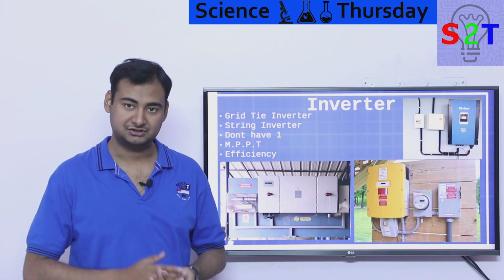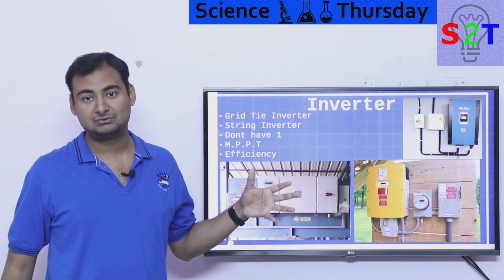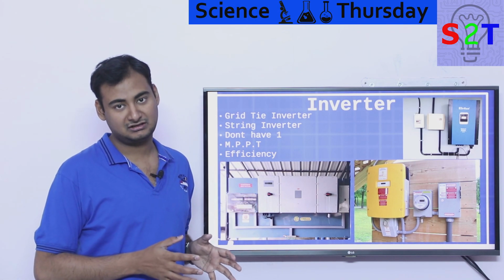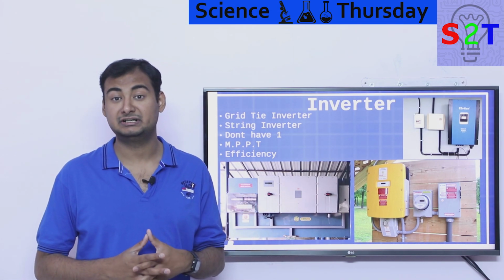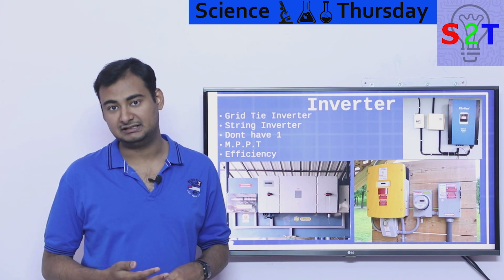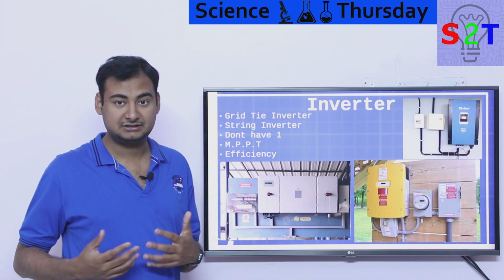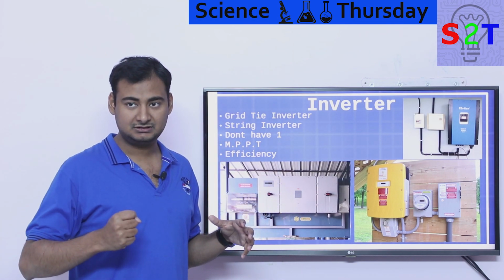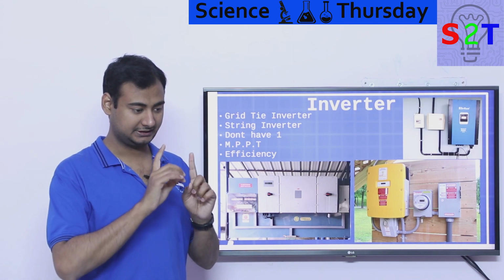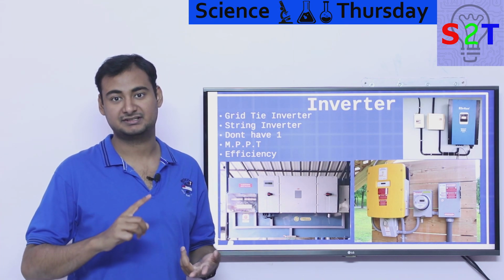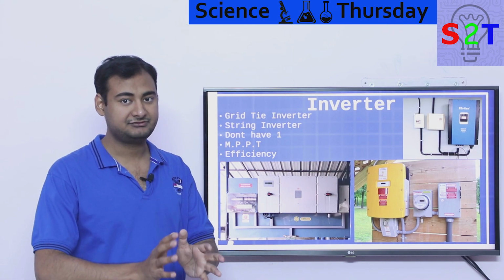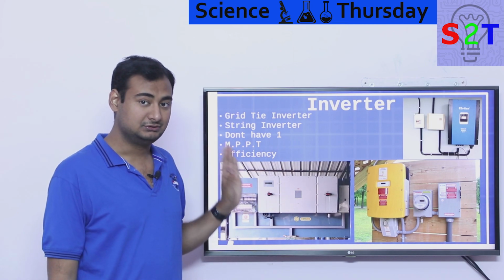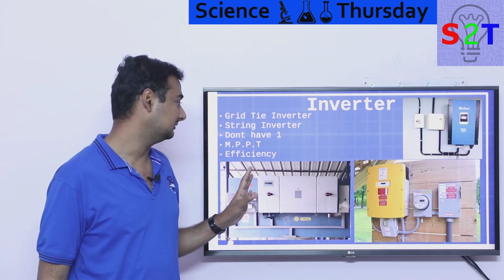How the phase angles are, the inverter is going to take care of it. So it basically allows you to sync. Basically this acts like a generator. It takes the DC power and stores it in a capacitor bank. Sometimes you can buy inverters that don't even have transformers in them. Those are generally high efficiency ones, and that way you can get even higher efficiency and longer lifespan. So the grid tie inverter takes the grid power and uses it as a reference: this is how much power I'm supposed to get, this is my frequency and angle, and it syncs everything. The output from your solar farm goes to the grid because of the grid tie inverter. So this is basically the bread and butter of your livelihood.